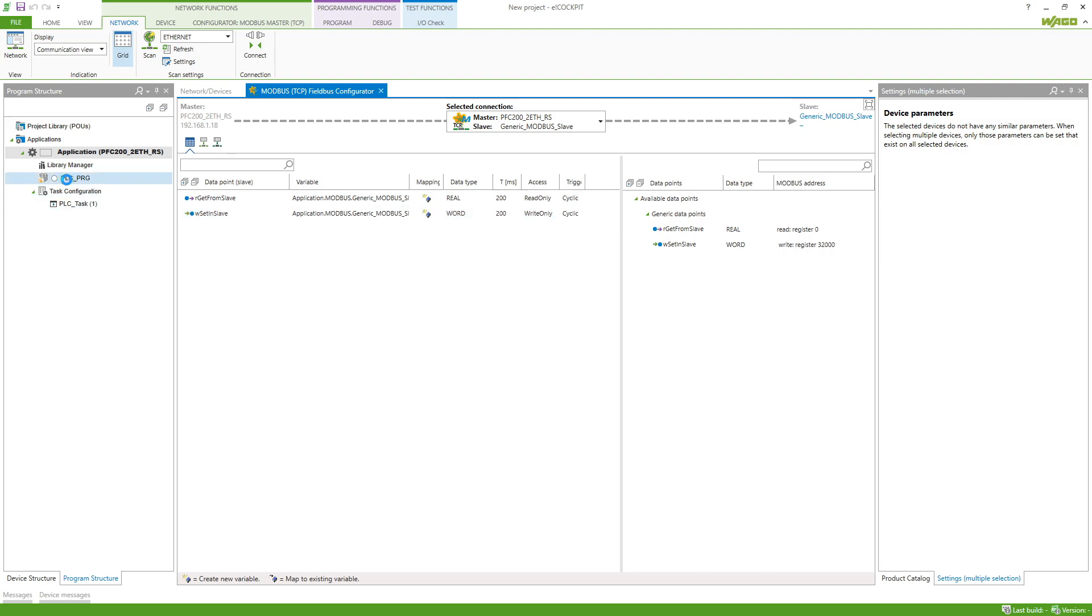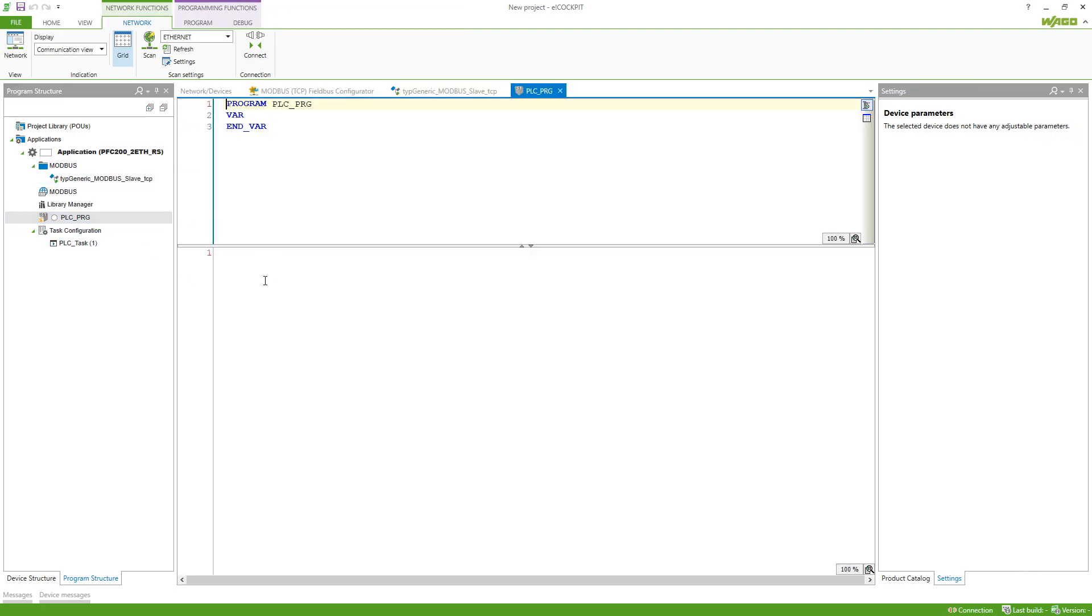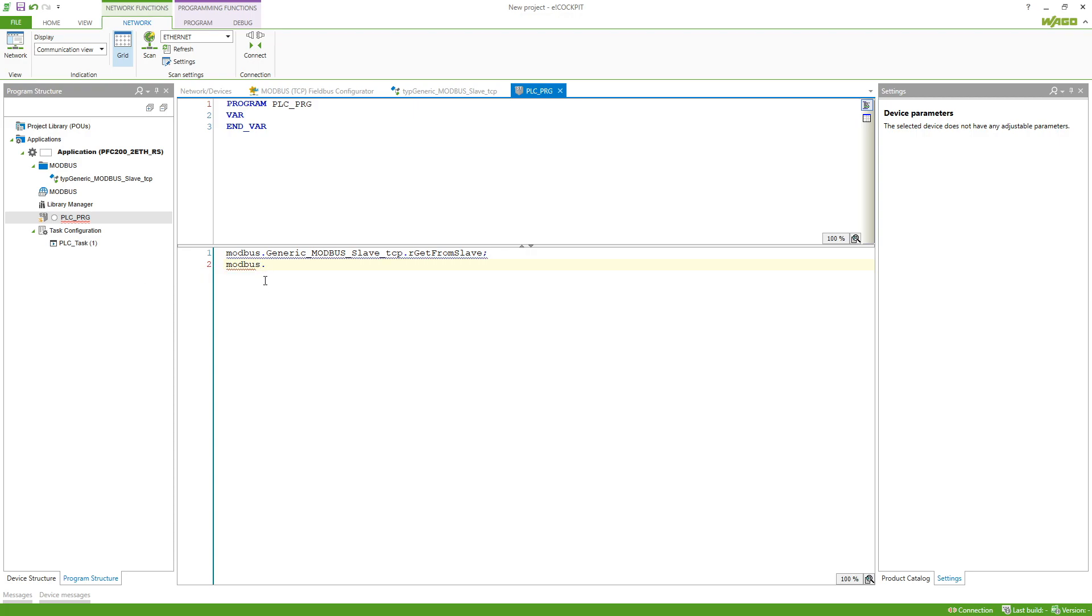Now if I go to the PLC PRG we will see that it creates the Modbus view. I can type in Modbus, then name of the slave and name of the variable. I will just call those variables for now so we can see what is happening. Again, name of the slave and the name of the variable, and then connect to my controller.